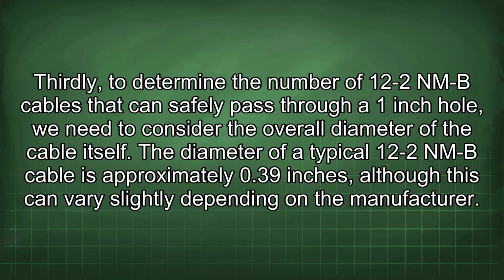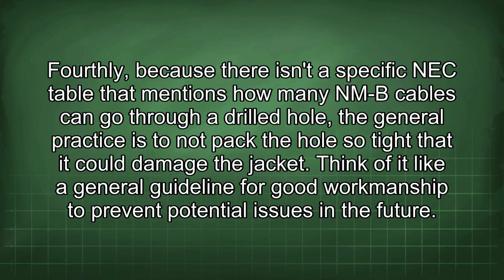Thirdly, to determine the number of 12-2 NM-B cables that can safely pass through a 1-inch hole, we need to consider the overall diameter of the cable itself. The diameter of a typical 12-2 NM-B cable is approximately 0.39 inches, although this can vary slightly depending on the manufacturer. Fourthly, because there isn't a specific NEC table that mentions how many NMB cables can go through a drilled hole, the general practice is to not pack the hole so tight that it could damage the jacket. Think of it like a general guideline for good workmanship to prevent potential issues in the future.